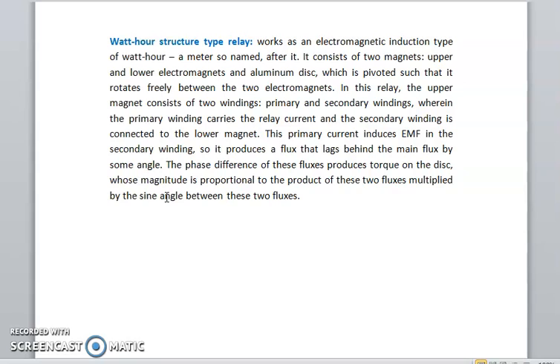Watt-hour structure type relay works like an electromagnetic induction type watt-hour meter, so named after it. It consists of two electromagnets, upper and lower, and an aluminum disc which is pivoted such that it rotates freely between the two electromagnets. In this relay, the upper magnet consists of two windings, primary and secondary, wherein the primary winding carries the relay current and the secondary winding is connected to the lower magnet.